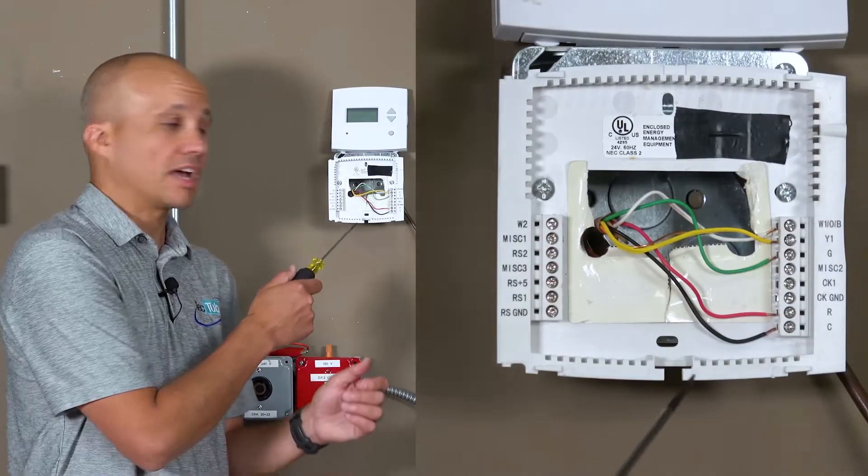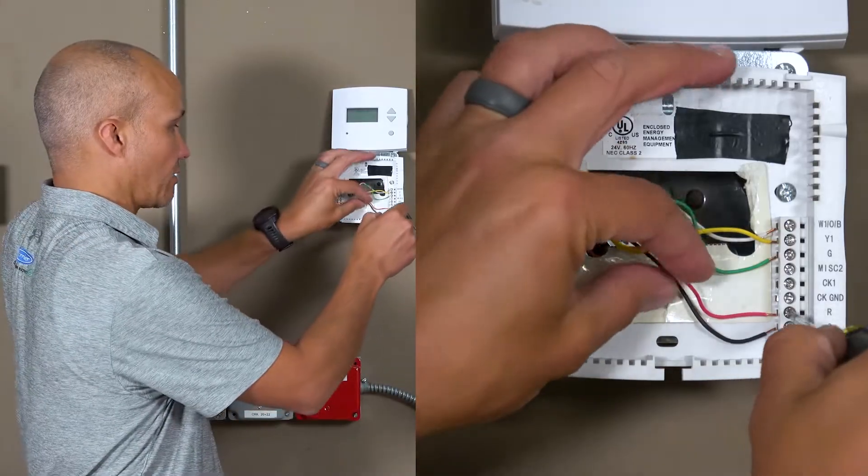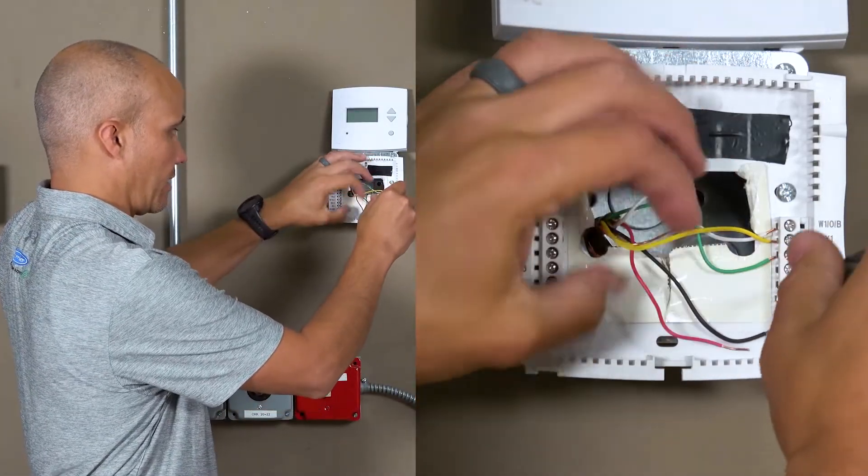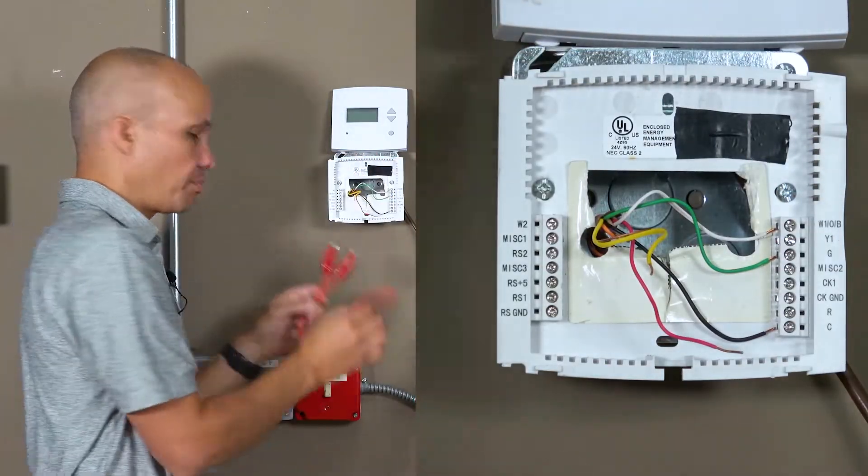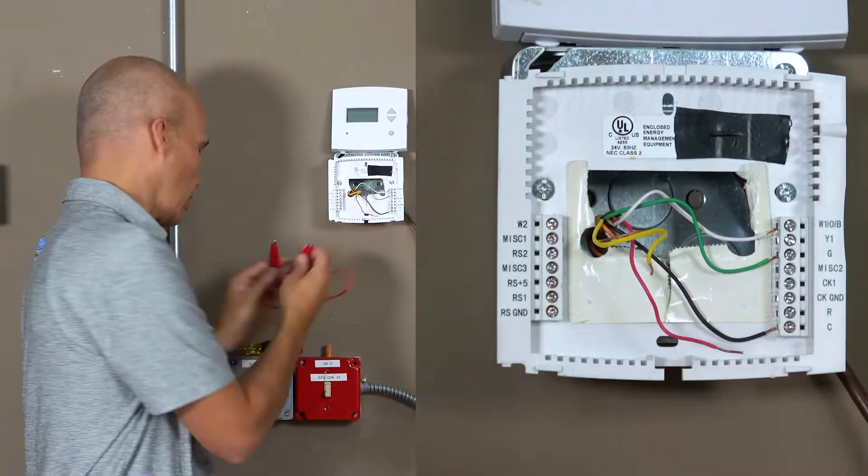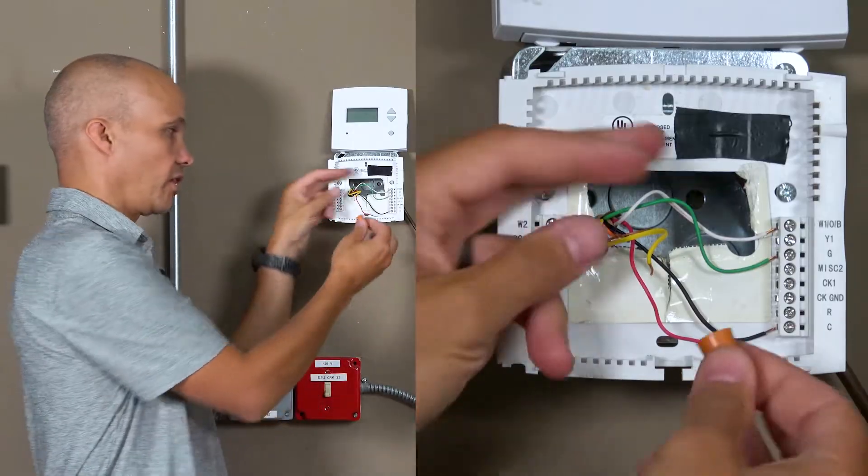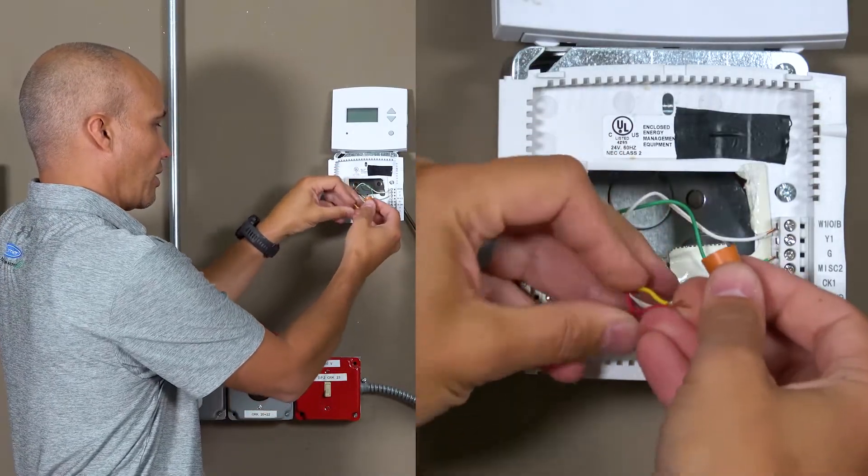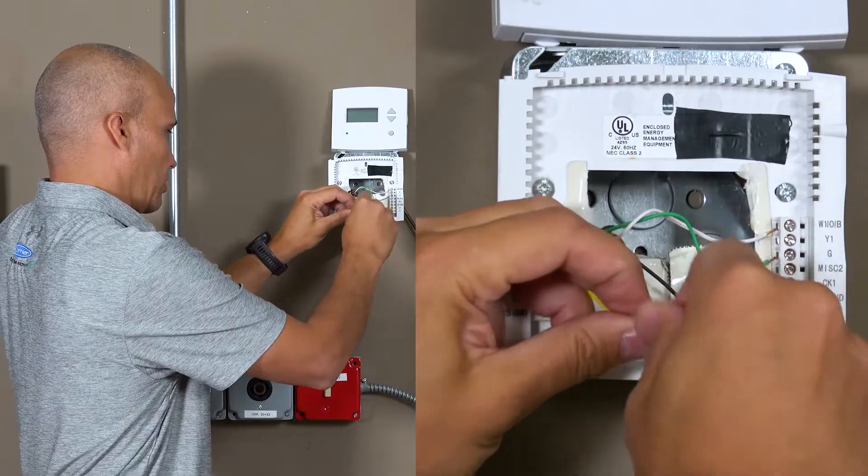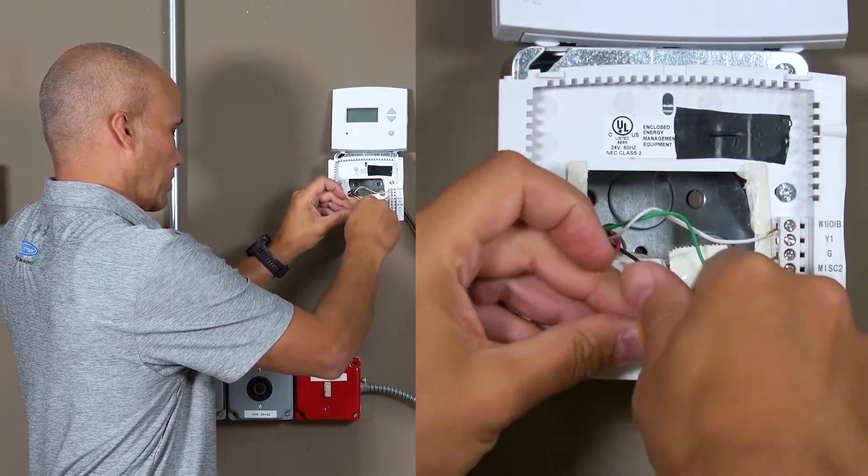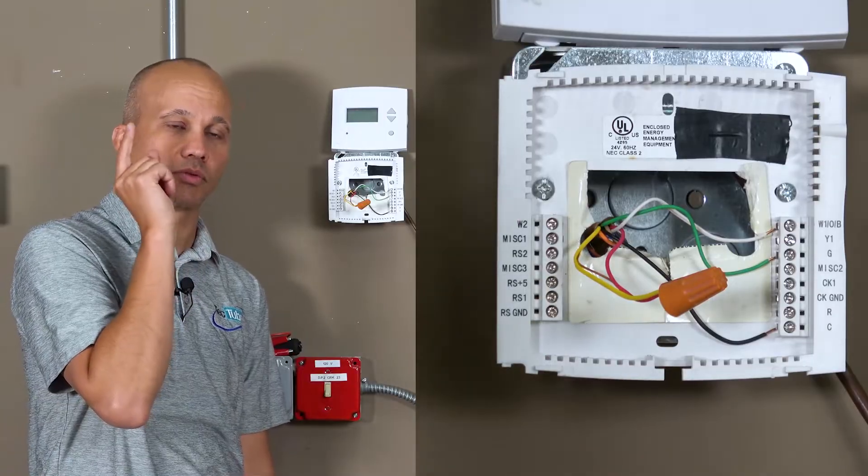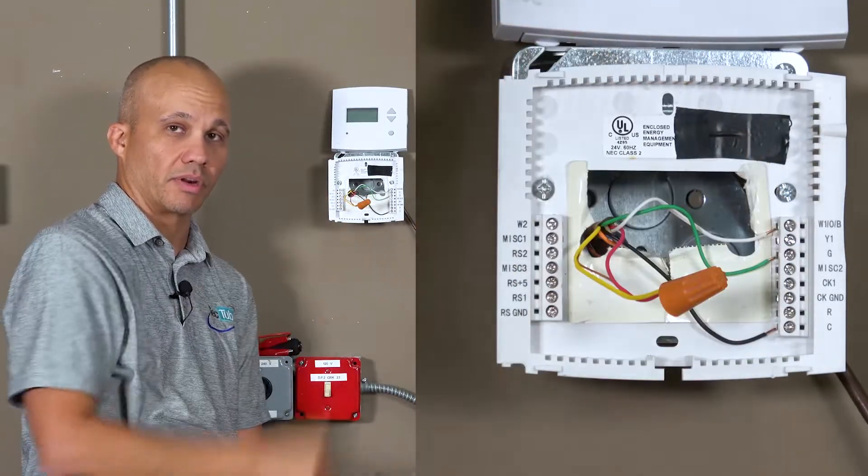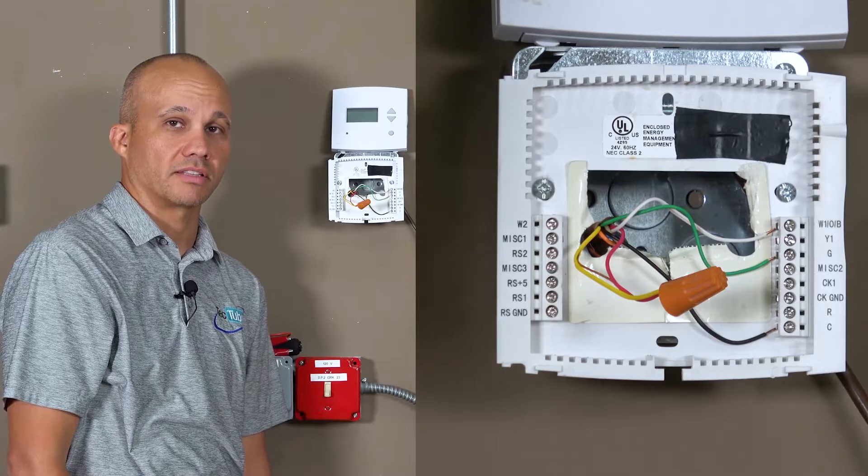We're down here at the thermostat. We're going to disconnect in this case the red wire and the yellow wire and then using our jumper we're going to connect the two of them together or if you prefer you can use a wire nut. So now the red and yellow wire are one continuous loop from the rooftop unit down to the stat and back to the rooftop unit. So let's go upstairs with our meter and test it.